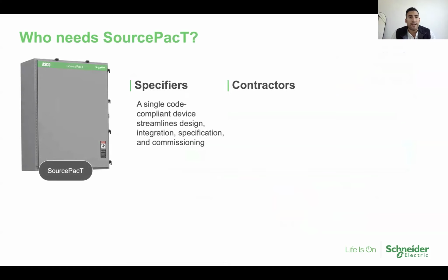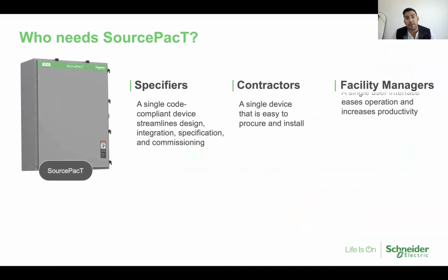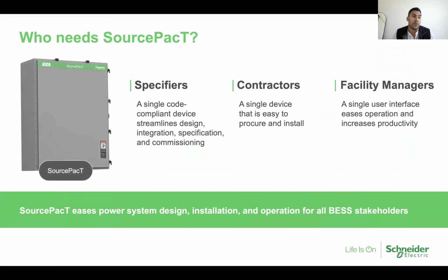So who needs SourcePacT? We like to start off with specifiers. This is a new product in a new industry, right? And to Victor's point, energy storage systems have just been accepted in the National Electric Code as an acceptable means for emergency standby power. So with this, a lot of education on the UL listing, how the product is applied. This is an automatic interconnection switch. It's a little different than a transfer switch, but it entails all the same testing criteria and robustness that goes into a transfer switch testing product.